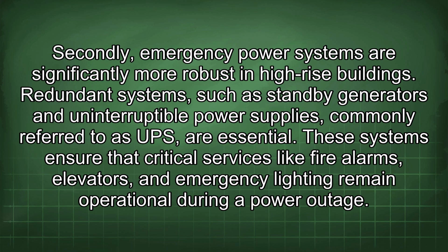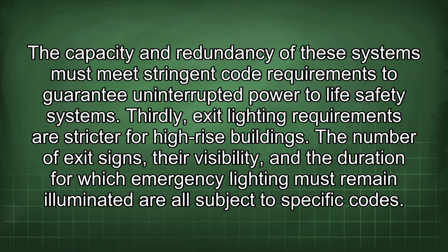Secondly, emergency power systems are significantly more robust in high-rise buildings. Redundant systems, such as standby generators and uninterruptible power supplies, commonly referred to as UPS, are essential. These systems ensure that critical services like fire alarms, elevators, and emergency lighting remain operational during a power outage. The capacity and redundancy of these systems must meet stringent code requirements to guarantee uninterrupted power to life safety systems.